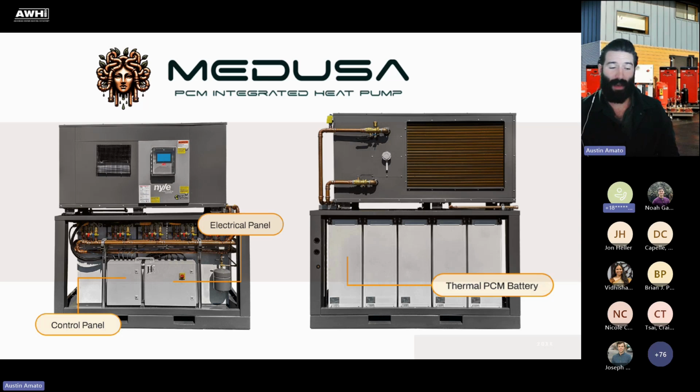The one application I would not suggest this product for is a specific lab situation or kitchen where 140 degree water is required at the fixture. The melting point is 136, and while we can take the material above 136 and dump some more sensible heat into it, the vast majority of the time, the water leaving this unit is going to be 136. So I just want to throw that out there. The intention was to build a unit that addressed all of these market barriers, but that's one application I would just not suggest it for.